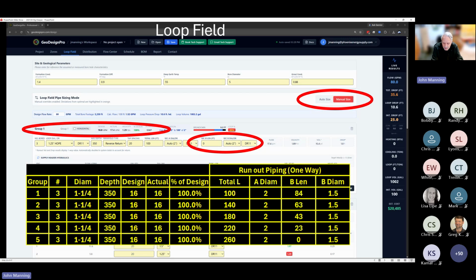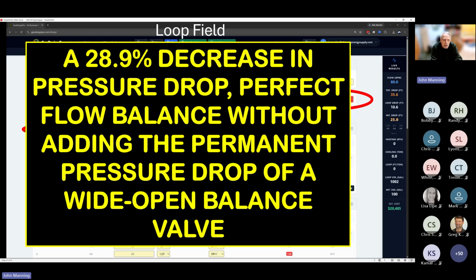let's look at it a different way. Let's take that furthest circuit and we're going to convert it to 3-inch as the runout diameter. And then we're going to balance it by using different lengths of 2-inch on each of those runout pipes. And we've still achieved 100% balance. Yes, we spent a little more money on pipe, but at the end of the day, we've achieved a 28.9% decrease in pressure drop. We've achieved perfect balanced flow without adding the permanent pressure drop of a wide open balance valve that simply translates to more pumping energy than what the system should have.